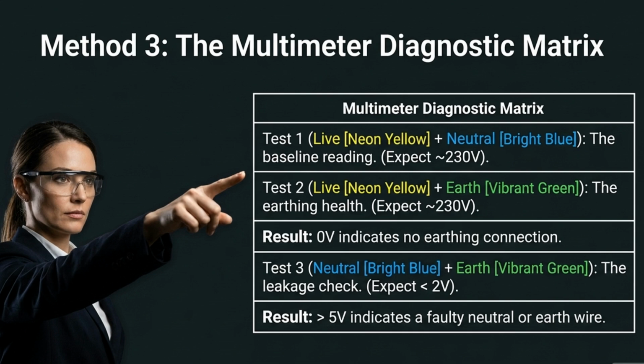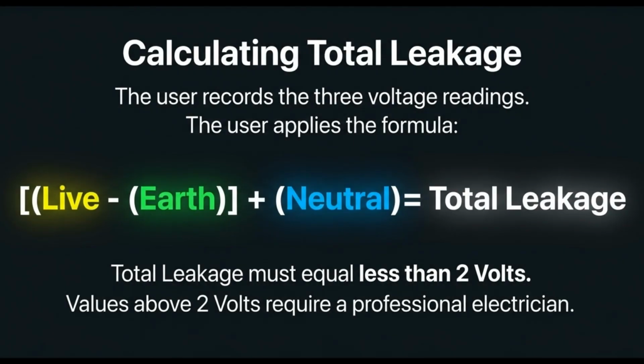Measure between live and neutral for a baseline, live and earth for earthing health, and neutral and earth to check for leakage. To calculate total leakage, apply this formula using your 3 voltage readings. If the total is less than 2 volts, your system is fine. Higher values require a professional electrician.